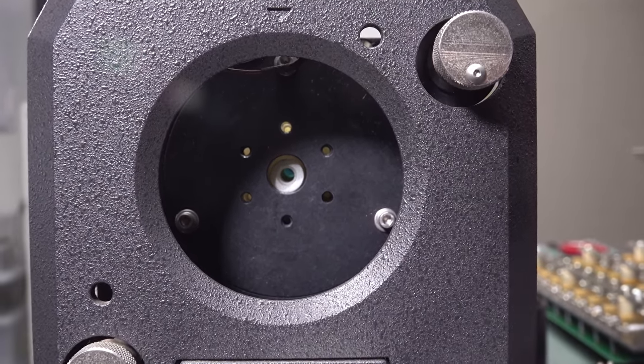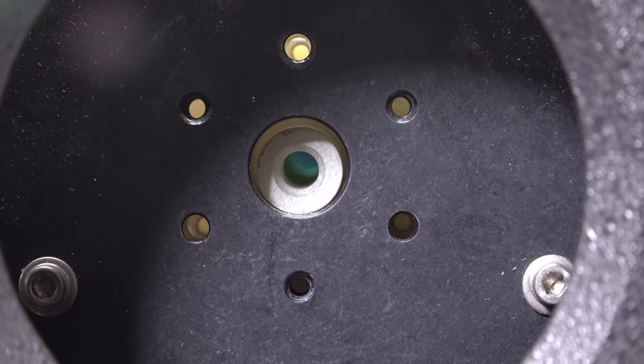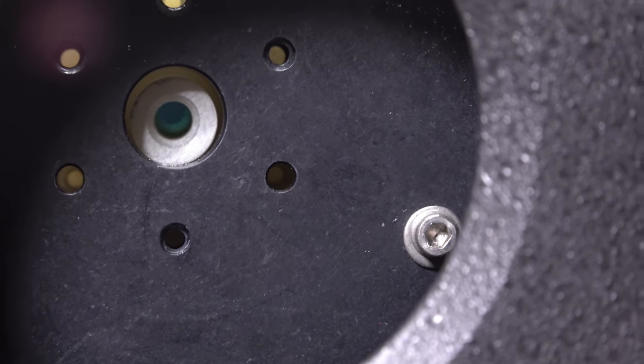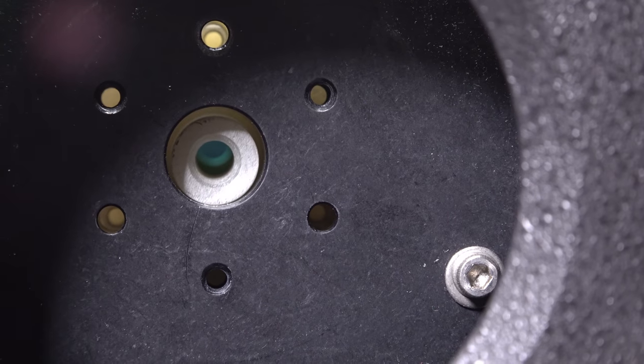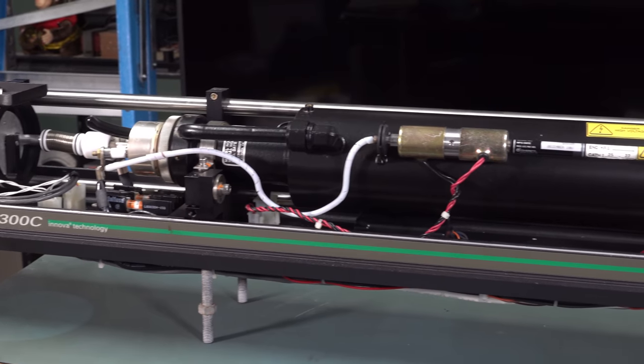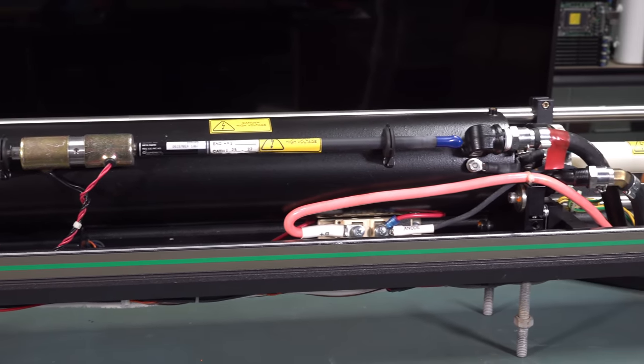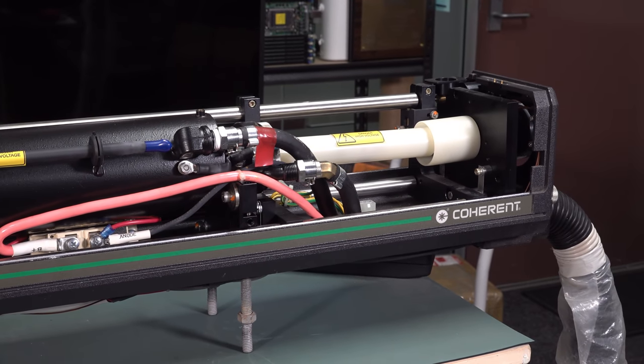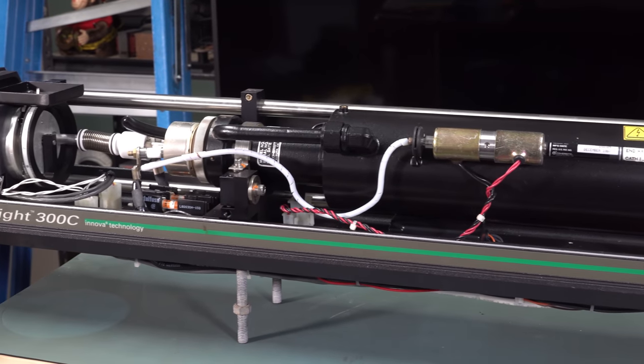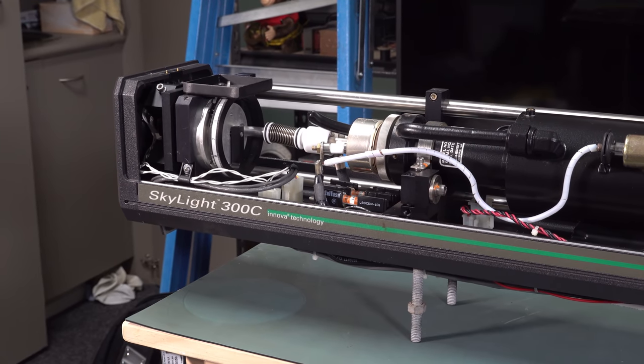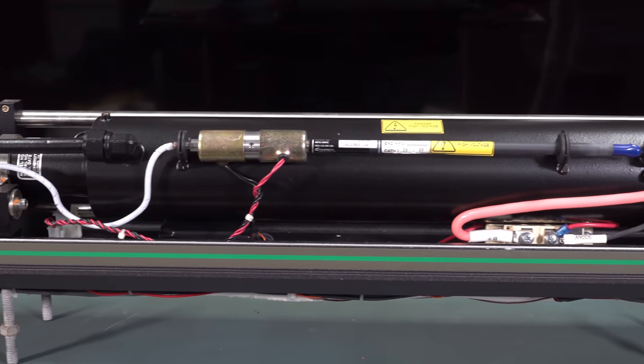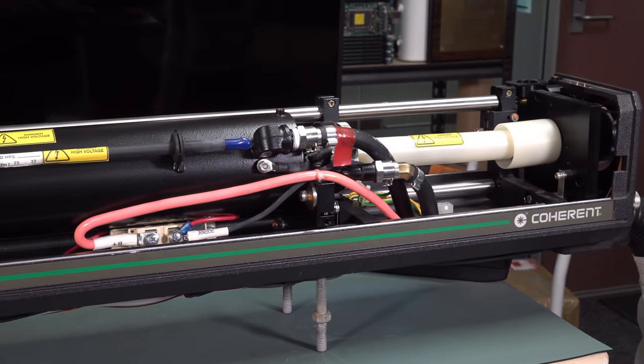And here's the other mirror at the other end of the ceramic tube. So this is the arse end. The cable side. And you can probably, yeah, you can probably just see some reflection in the mirror there. You might even be able to see the camera or something like that. But that's the end of the, that's once again the hermetically sealed end of the ceramic tube. So that's just what's behind the metal cap on the end. It's just the end of the rear mirror there. So there you go. I hope you enjoyed that teardown as much as I did. Absolutely fascinating. Look. Inside an Argon Ion laser. As I said, this thing is in the order of twenty plus kilowatts for ten watts output. So yeah, it's a lot of waste heat. And they're remarkable things, but they still have uses these days. They are not obsolete.